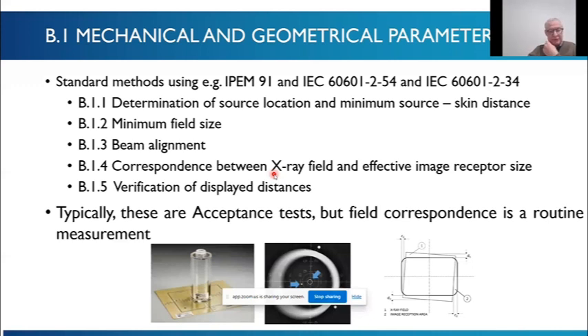The minimum field size, which should be 5 by 5 when expressed at 1 meter source image receptor distance. The beam alignment test, which is using this kind of tower with radiopaque markers, and then the correspondence between the X-ray field and the effective image receptor size. This is done as an acceptance test and also done routinely, because this can go out of tolerance, and you can ask the engineer to reset it or correct it over the lifetime of the equipment. It will change a bit. And then there's verification of display distances, which involves measuring with a tape measure. So quite simple tests.